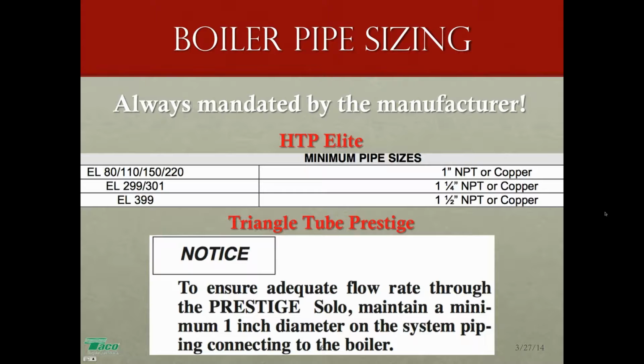I'll tell you that. If you've got to look up in your schematics or your specifications for the indirect, make sure you know the flow rate through the heat exchanger for the indirect to get the recovery you need. Size that pipe properly, and then you've got to size your circulator to overcome the head loss through the heat exchanger, your supply and return piping, and the head loss in the boiler itself. When you do all that math, you'll find that you're going to need a fairly substantial circulator. Alrighty, let us continue.